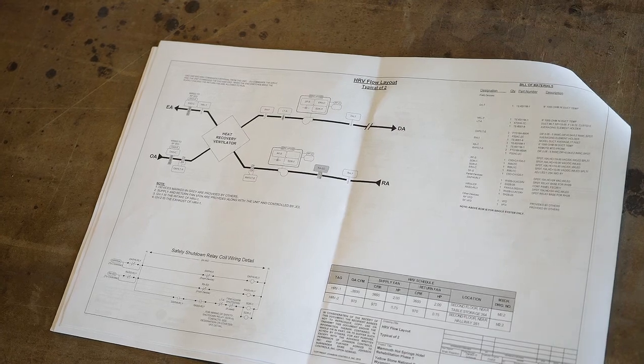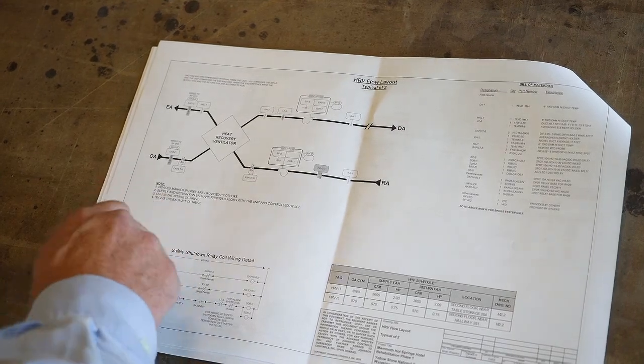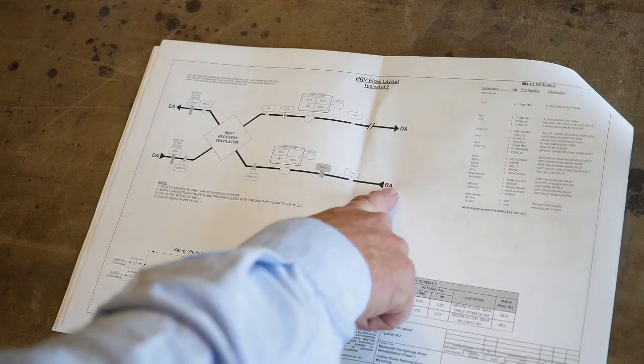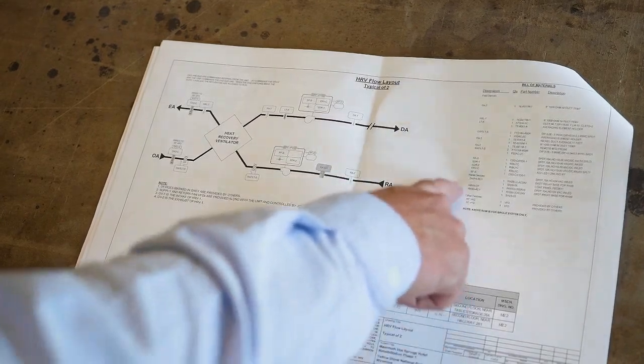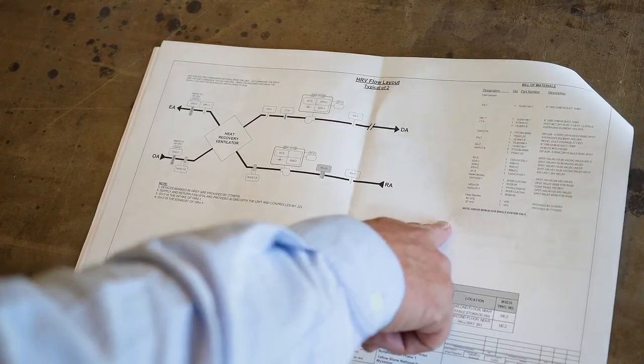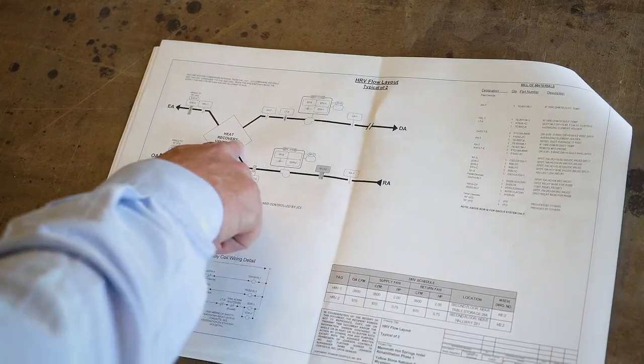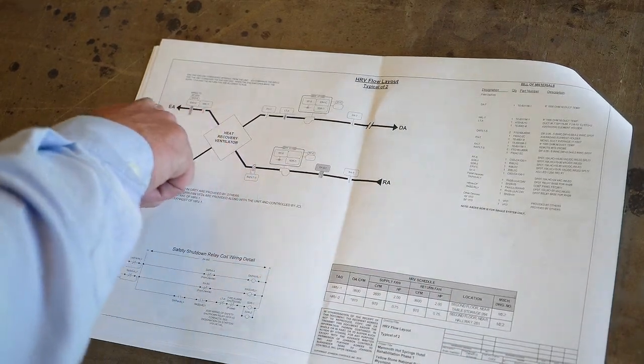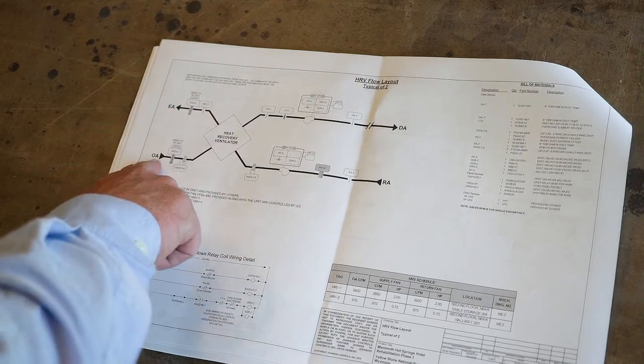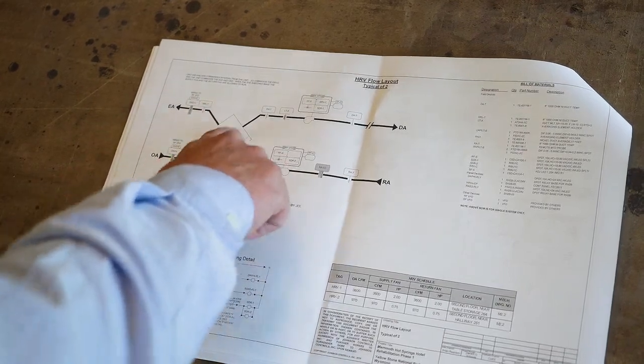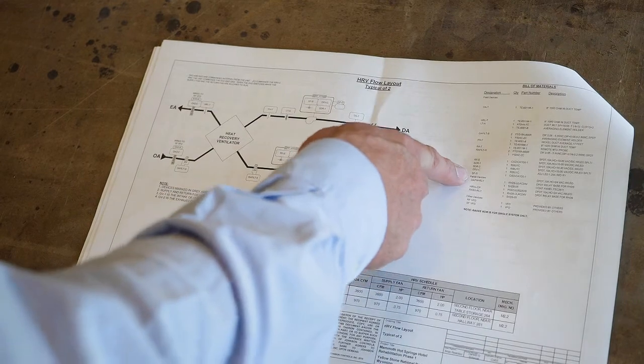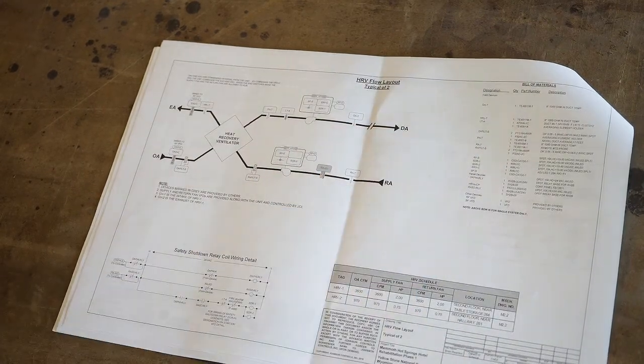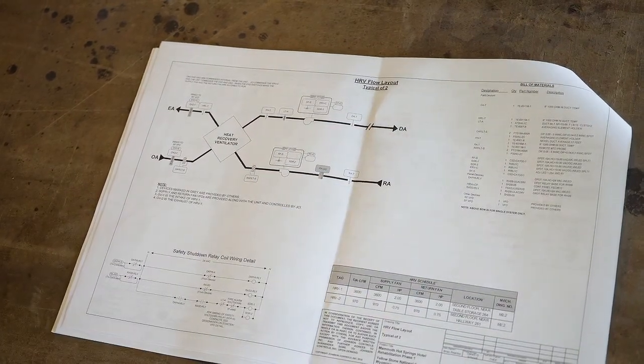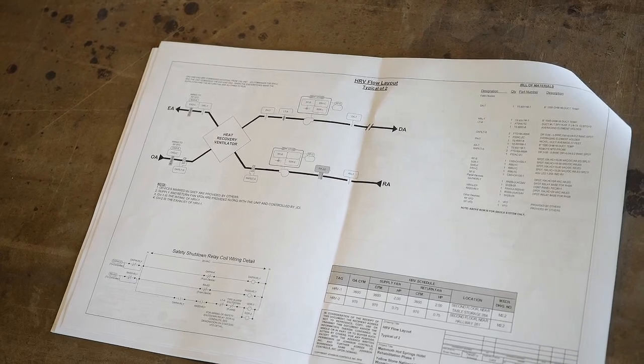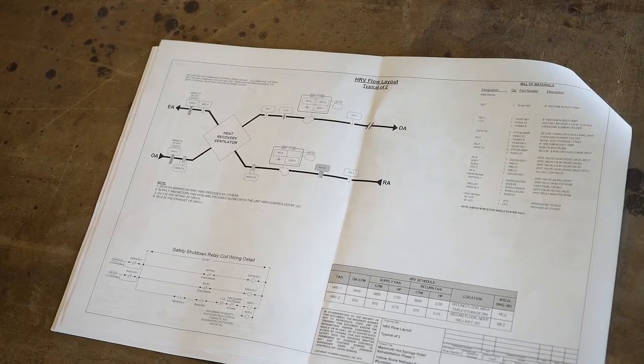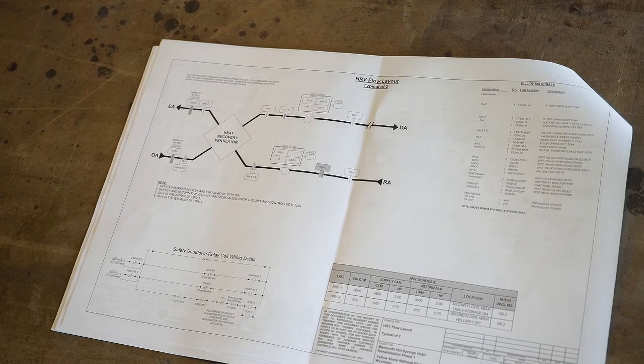Correct. So a lot of times what they'll end up doing is they will take this return air and pull it out of the bathroom areas, any place where they need to exhaust air from. They'll pull it up through the heat exchanger on the heat recovery unit, and as the outside air is coming in, it will preheat that air before it blows down into these rooms. And that happens in that cell he was talking about, that every 5 years or whatever we've got to wash. Pay attention to that.